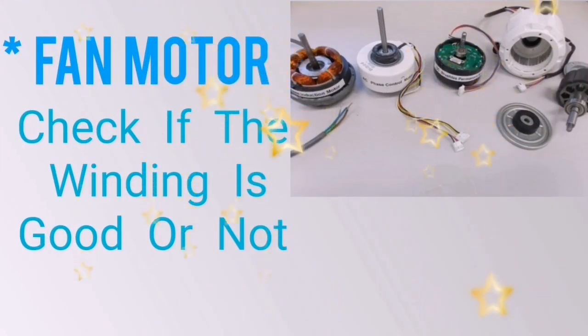Step 3. Then we have to check the fan motor. The fan motor helps to rotate the fan. When the fan rotates, it removes the heat from the condenser, which brings the refrigerant to a lower temperature and protects the compressor from overheating. If you have checked the running capacitor is good and the fan is not rotating, it means the fan motor is faulty.